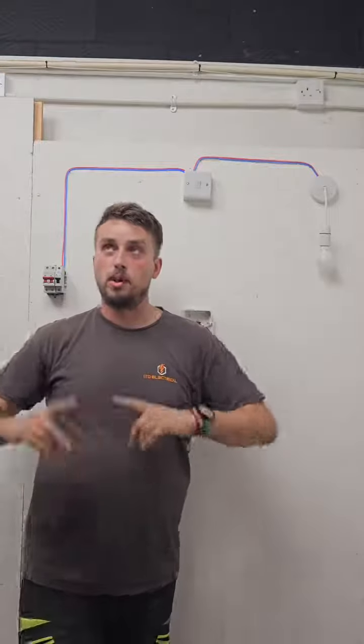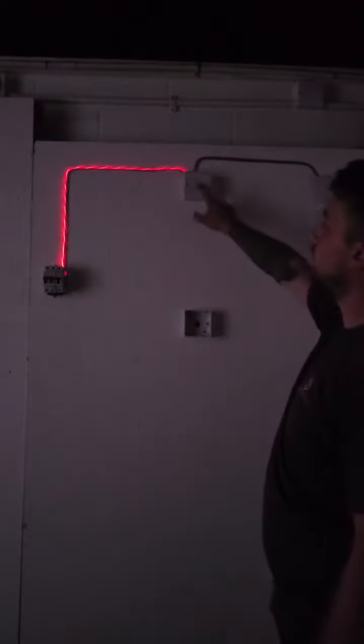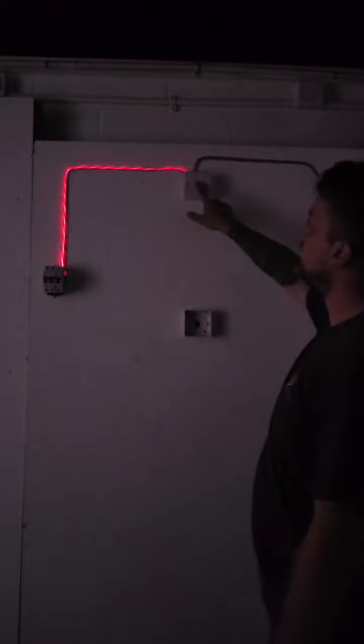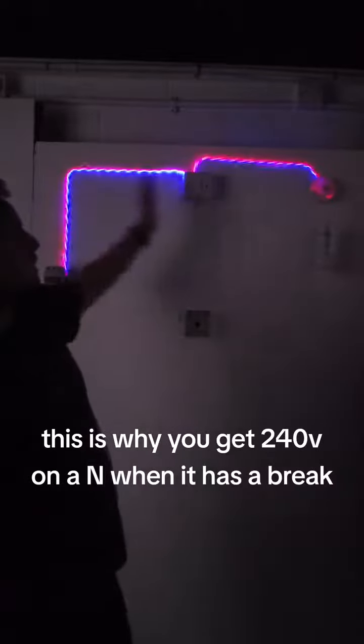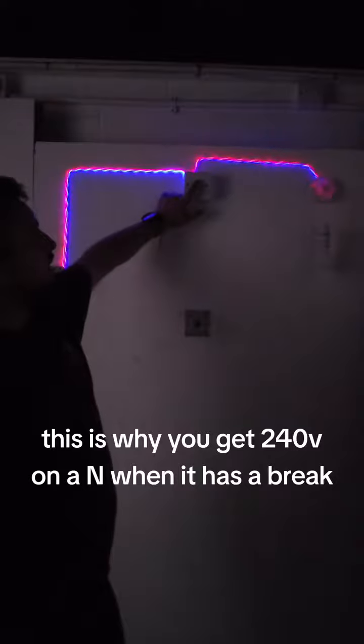And we're going to demonstrate how that flow of electricity works by turning off the lights. So when your breaker goes on, your current flows through your brown wire up to the common of the switch. So when you turn your switch on, it bridges from common to L1, which will then send your current up to the pendant. And when and only when your lamp's in, it completes the circuit, sending your voltage back on your neutral, or at least getting your potential difference across line and neutral here to send your voltage back.